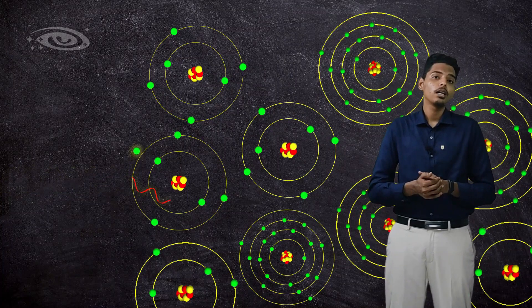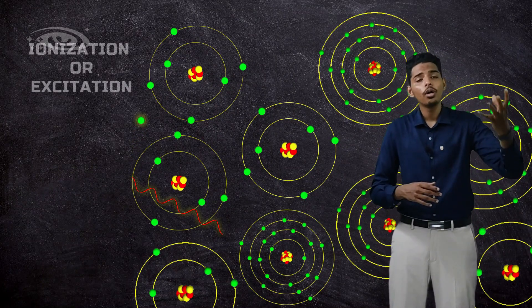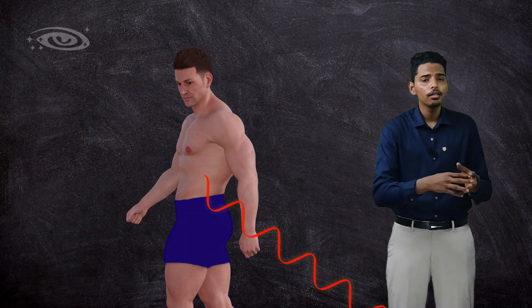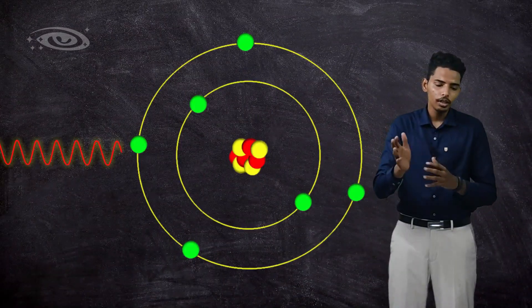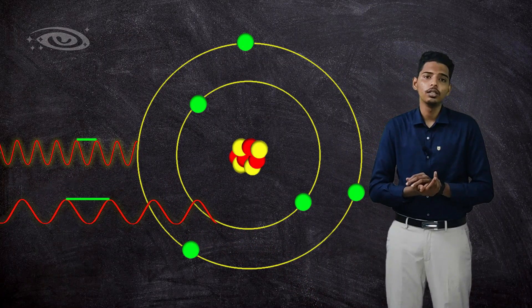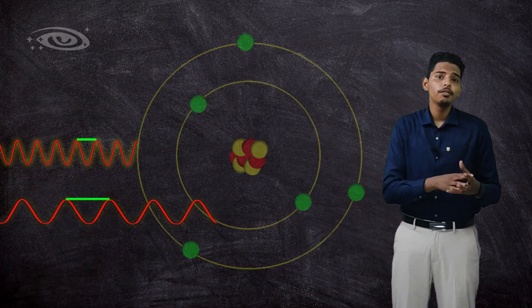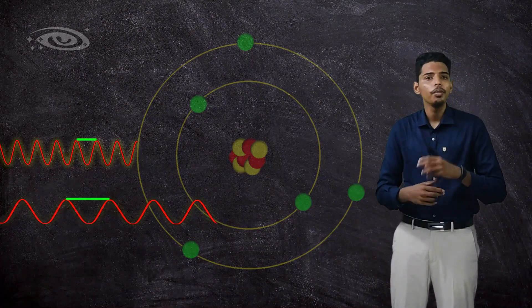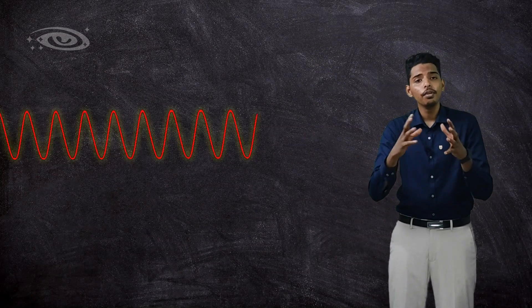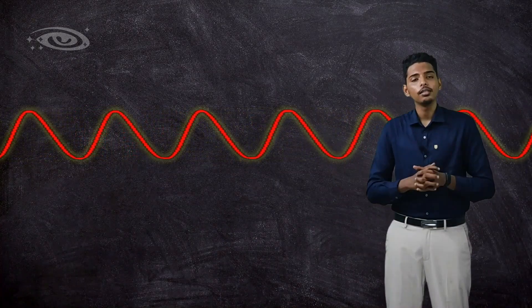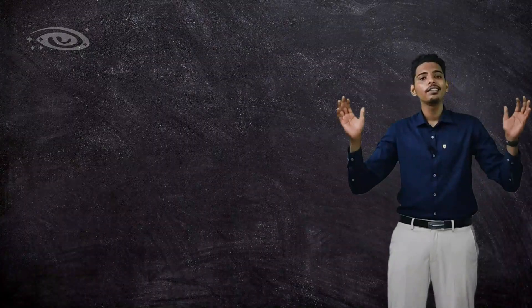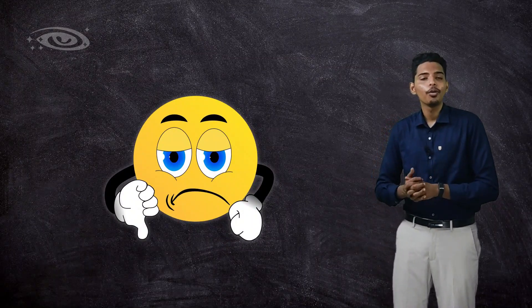The ionized electron and the scattered X-rays will have sufficient energy to cause another ionization process in neighboring atoms of the matter, or they may exit the matter without further interaction. The scattered X-ray photon energy and wavelength differ from the incident photon — the scattered energy is less because energy was transferred to the electron. When X-ray energy decreases, the wavelength becomes longer, since X-ray energy is inversely proportional to wavelength. Compton scattering is therefore not useful for producing an image — it just produces noise in the radiographic image.